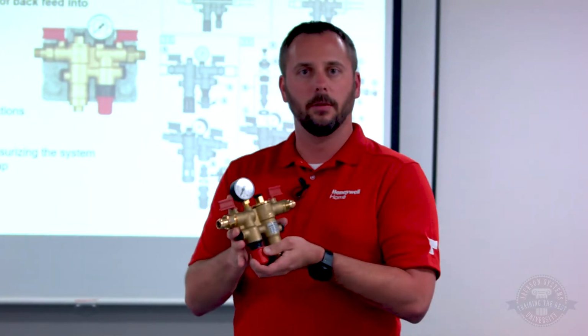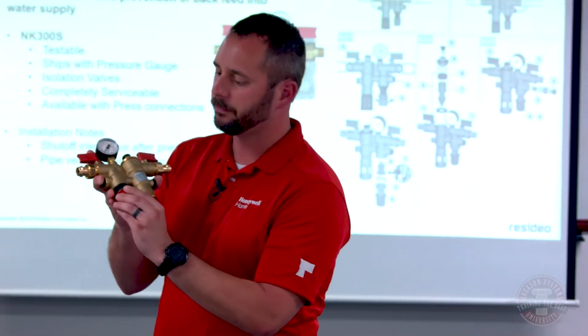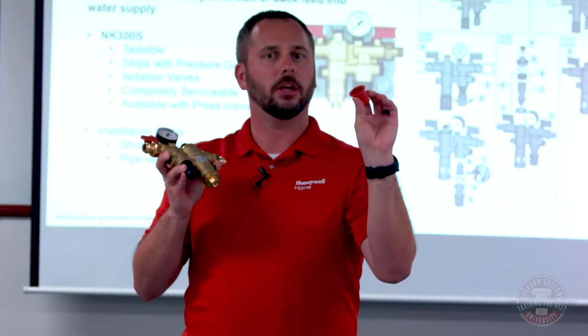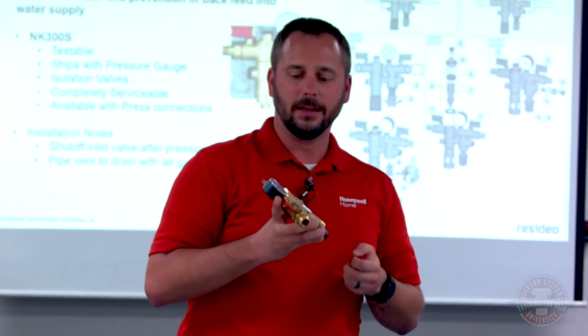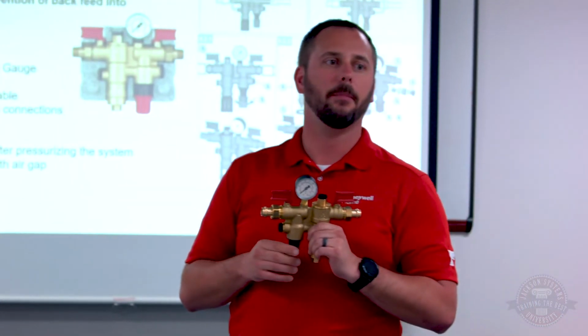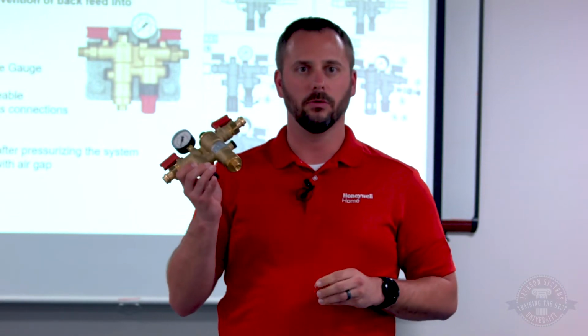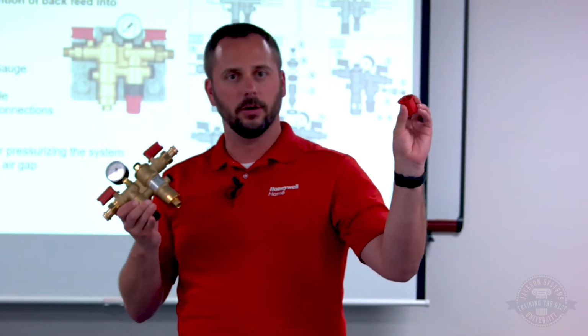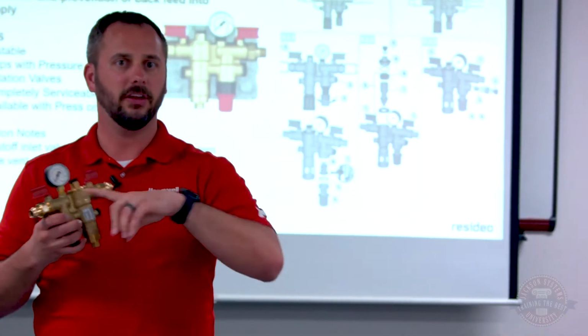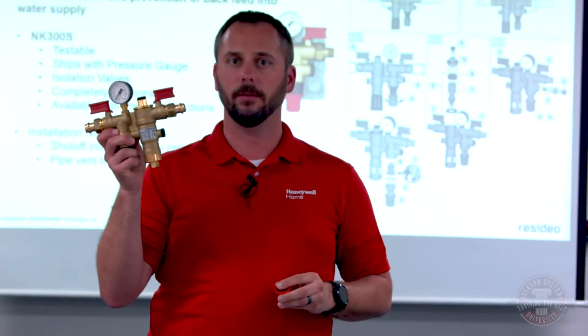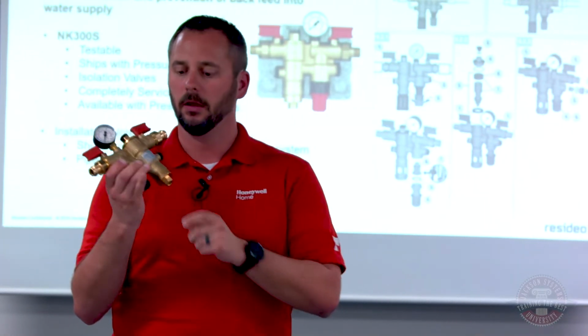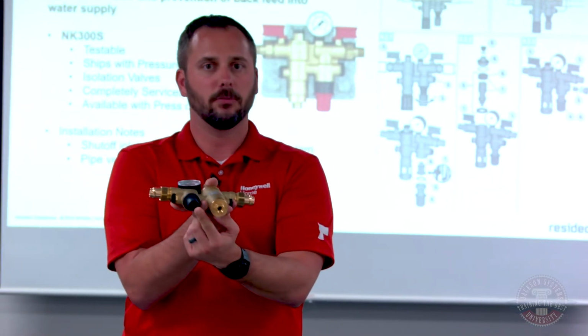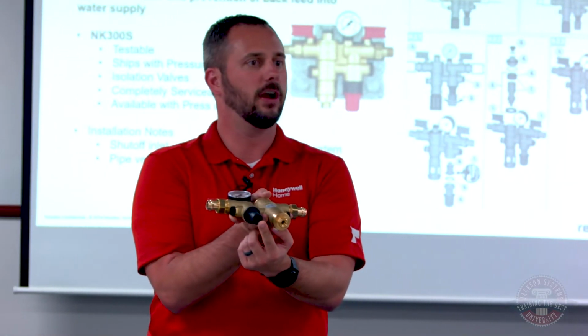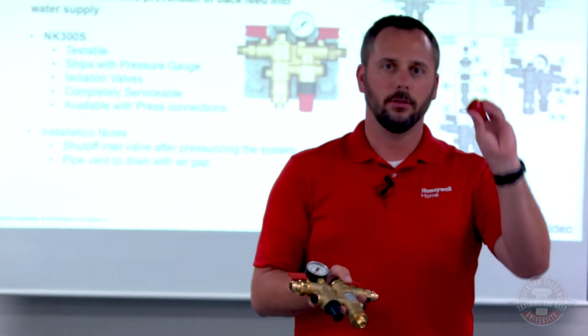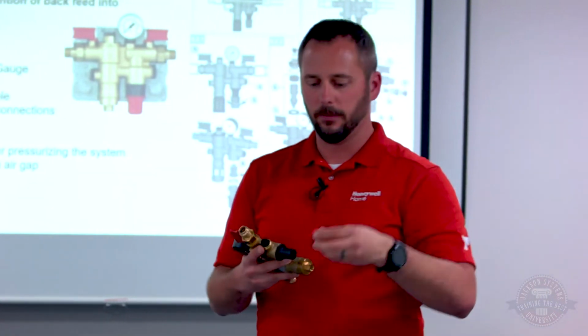The PRV down here on the bottom, just as a setup installation, ships with this little plastic adjustment tool out of the box. As I had mentioned with the previous cap, homeowners love to play with things that move. So you can use this to set your initial pressure rating, which this is set at 15 pounds, but you'll be adjusting that when you fill it. Afterwards, throw this thing away, keep it in your truck, do something with it. And then here on the bottom, where you make your pressure adjustment, you can use just a standard flathead screwdriver to get in there and make the adjustment. So this is great on initial install. I would not keep it in there.